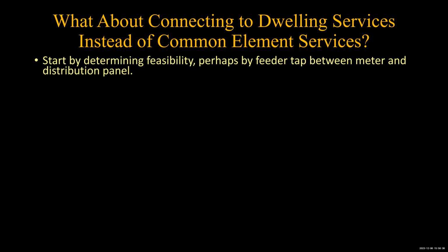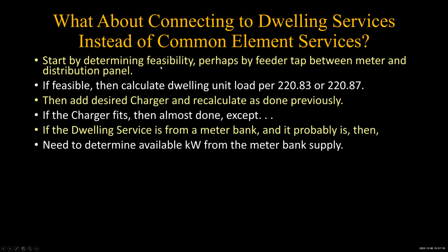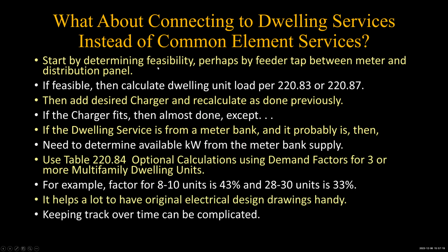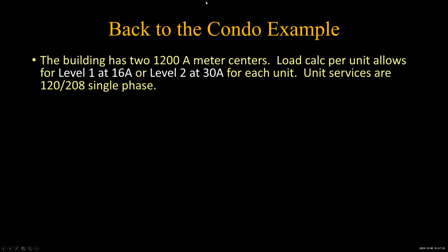So I'm just going to tell you, be really careful and do that calculation very carefully, because you're going to have to add not just to the one unit, but that one unit is connected to a bunch of meters, and it's probably got a single service. Like my building has 21 units on one 1200 amp service and 22 units on another 1200 amp service. And when you do the calculations on that, there's not much extra room for 125% of a level 2 charger on top of that. So watch that one really carefully. And the math is here. You can take a look at it if you're interested in it. Couple more questions.